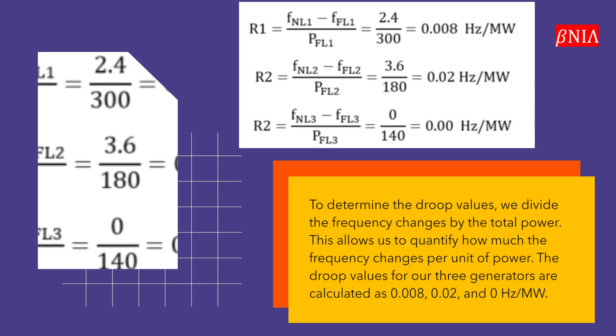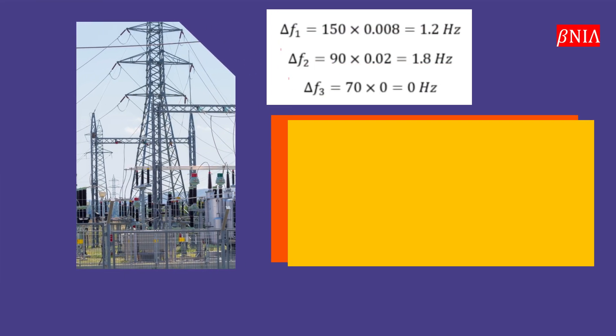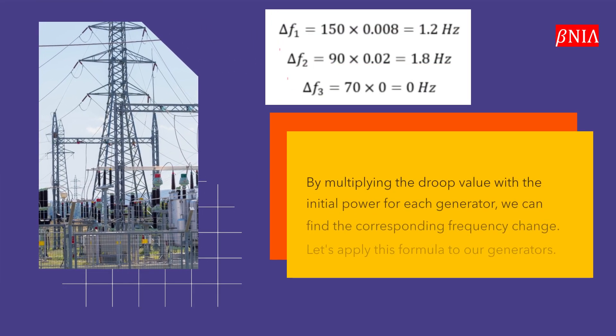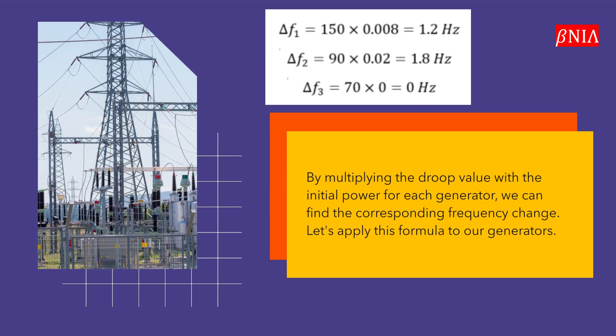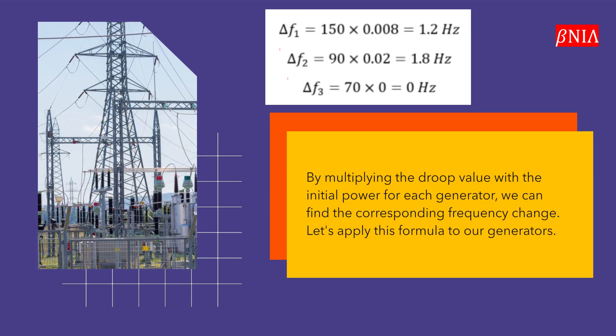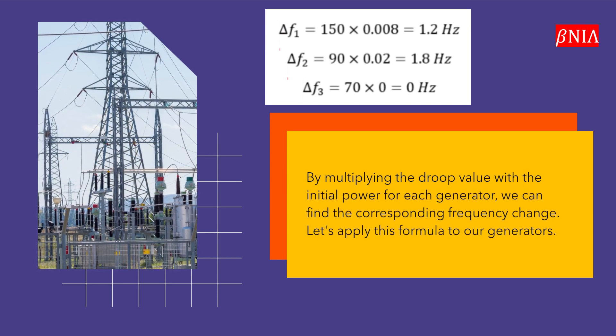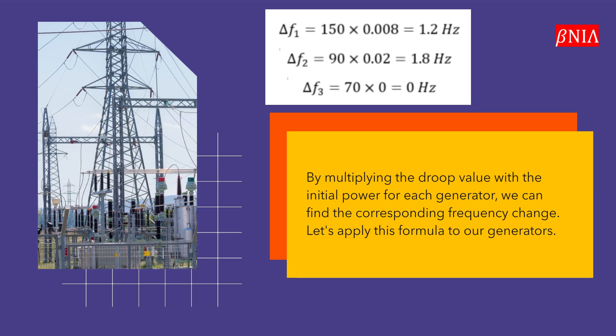The droop values for our three generators are calculated as 0.008, 0.02, and 0 Hz per MW. By multiplying the droop value with the initial power for each generator, we can find the corresponding frequency change. Let's apply this formula to our generators.